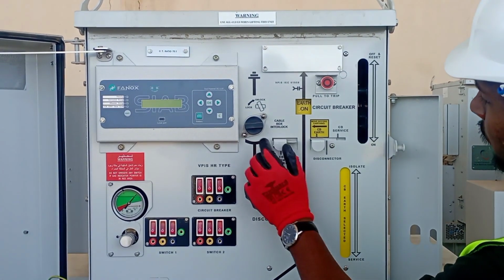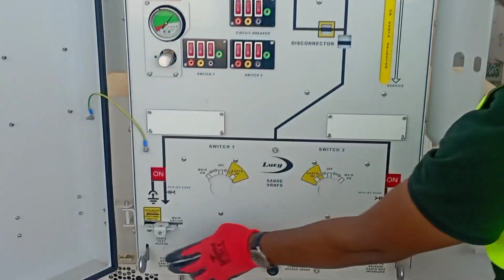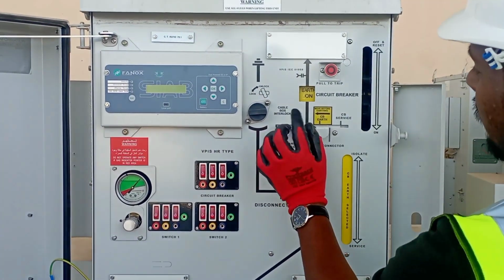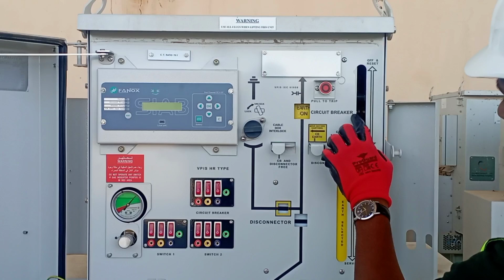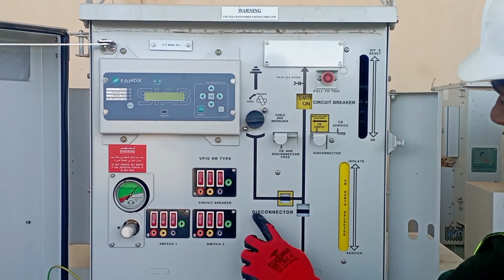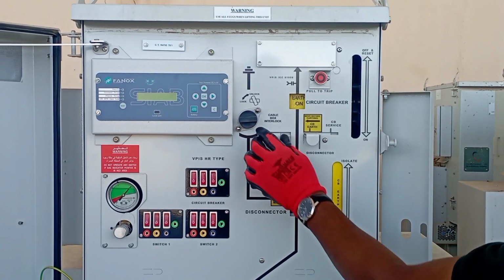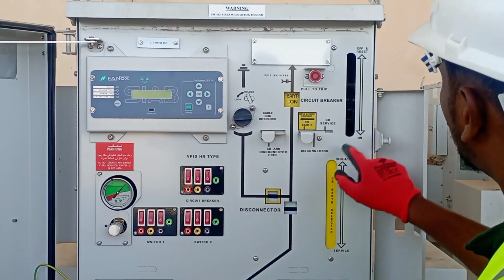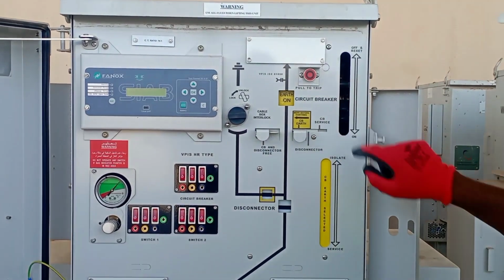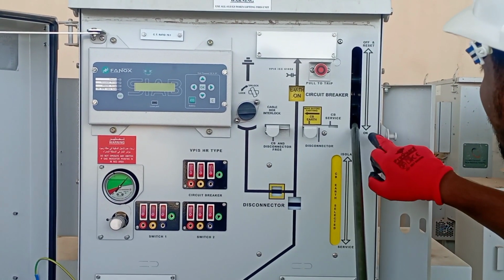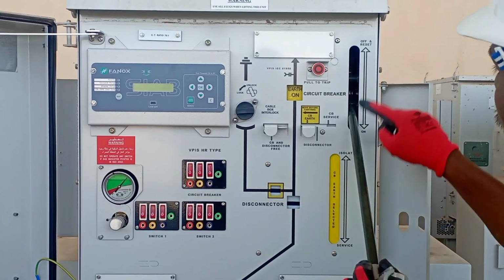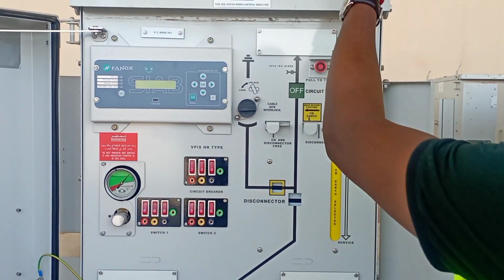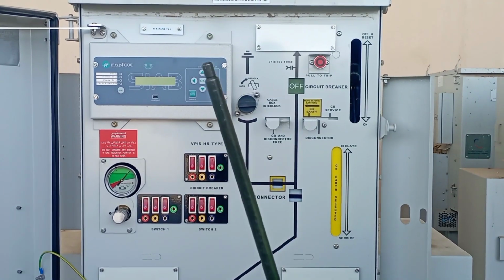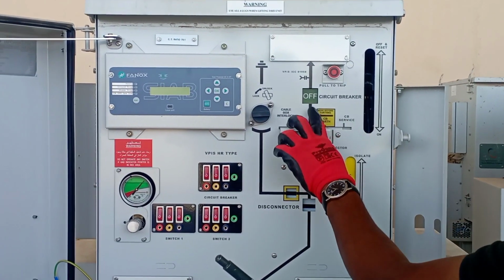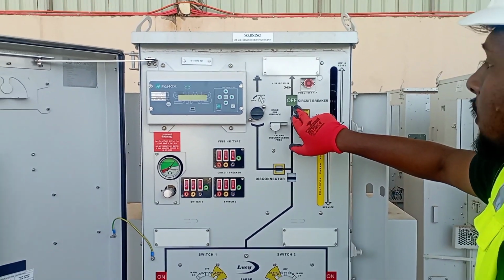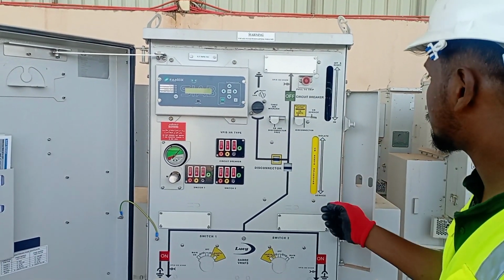Okay, there is two lever. It's not same as the main switch. We can see there is two lever. One lever indicates for this circuit breaker, and another one for this disconnector switch. Okay, for making on this one, we need to put the circuit breaker first in off position. Okay, now currently this one in on position, we have to put it in off position. So we are using this another end of this handle for making this one off position. So we can see here the earthing is now in off position.